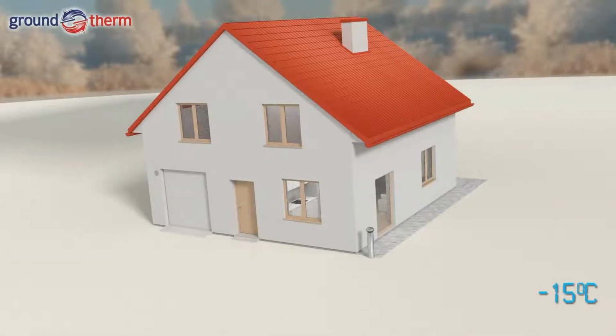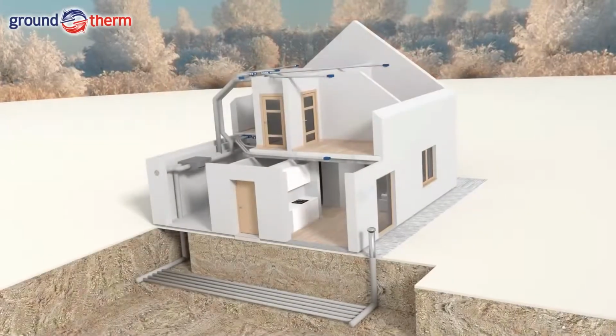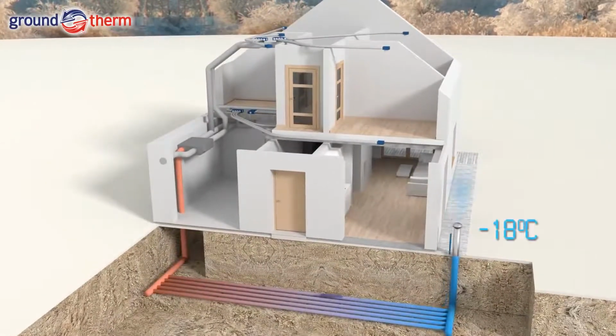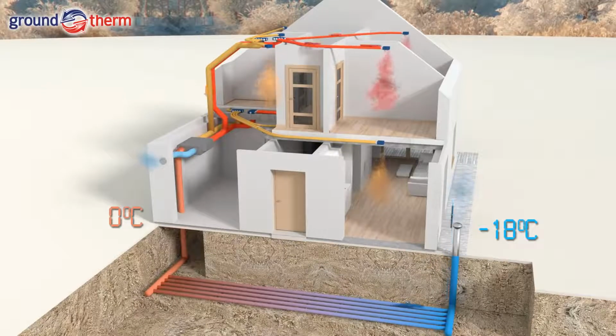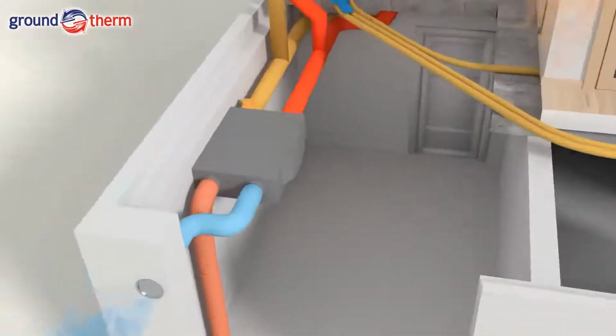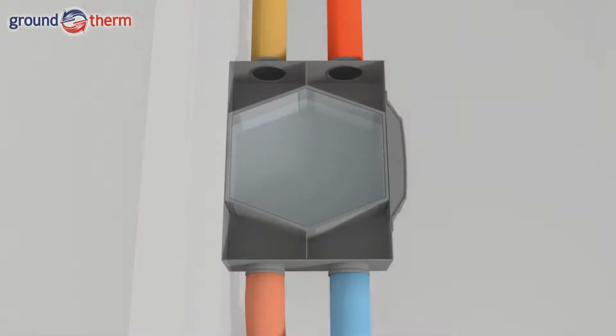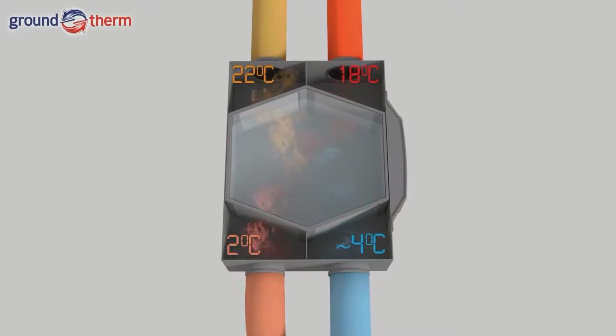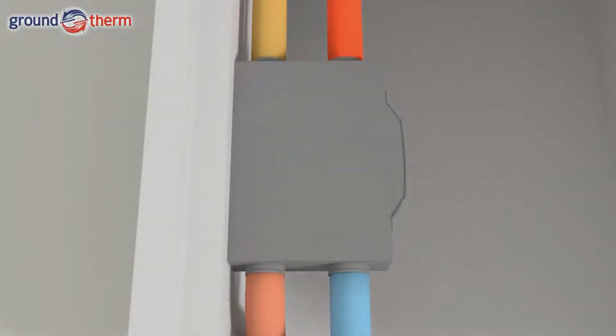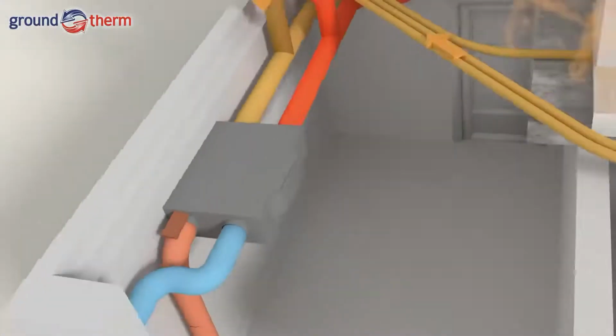In winter, before entering the building, the cold air is initially heated in the ground heat exchanger pipes to approximately 0 degrees Celsius or above. We obtain the additional free heat in this way. From the ground heat exchanger, the air is directed to the air handling unit that is the heart of the entire system. It is in it where, owing to the heat exchanger located there, occurs heat recovery from the waste air that is discharged from the building interior. In this way, the air entering the building achieves nearly room temperature, in other words, 18 to 20 degrees Celsius. Its further heating requires only very low energy input.